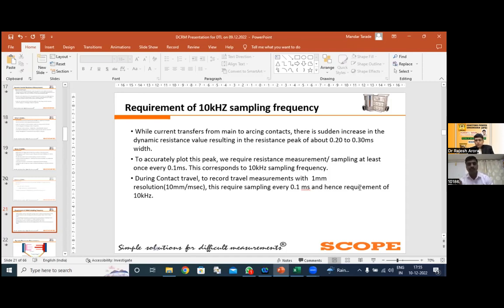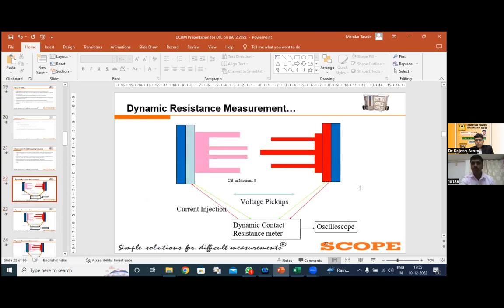Please remember that at the time of performing the DCRM test, our delay TCO must be equal to 300 milliseconds. At the time of performing the timing test, where we again perform the CO operation only, your delay TCO must be equal to your close time minus 10 milliseconds. I hope this point is clear to all.